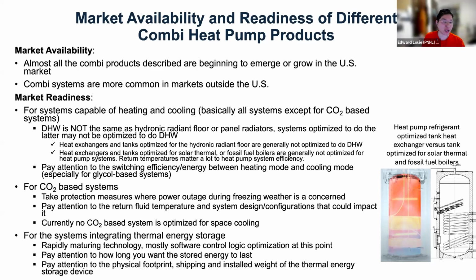So this is kind of my last slide. For refrigerant to glycol systems, pay attention to the switching efficiency, because that intermediate heat exchanger fluid needs to actually get cold if you go from heating mode to cooling mode, or from cold to hot when you're switching the other way.